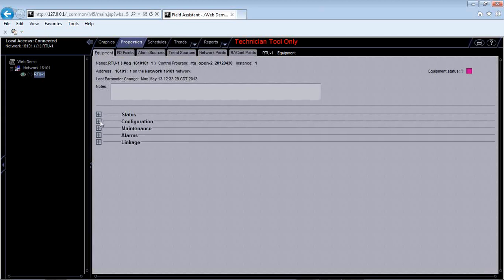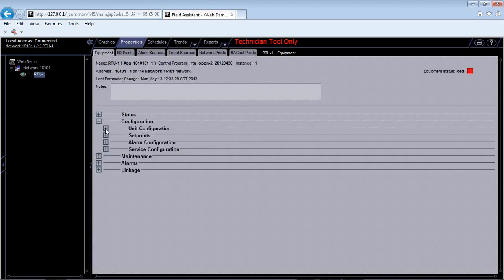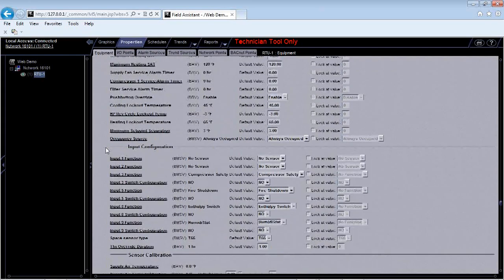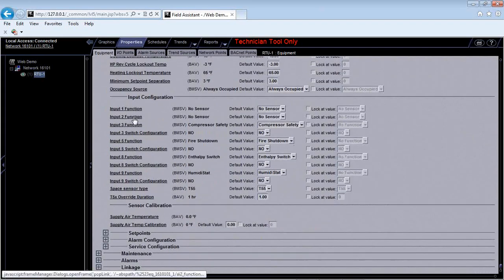Okay? So going back here, we're going to go to Properties, Configuration, Unit Configuration. And we are down to another important one, Occupancy Source. If I look at my drop-down, I have 4 different options. I have Always Occupied, which means I will run 365 days a year, 24/7, no matter what. No schedule, just cranking all the time. Generally, you'd use this if you're doing like a server room, maybe. But you don't really want to be controlling a server room with a rooftop unit in the first place. But that would just be an example of how you can use it.